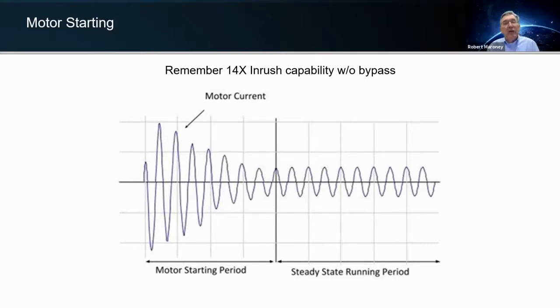And if you look at the inrush requirements to start motors, a static UPS does not like that. You'll deplete the DC bus, go to stored energy, and go to bypass immediately. And you can do damage to those types of systems depending upon what kind of motor you're talking about.